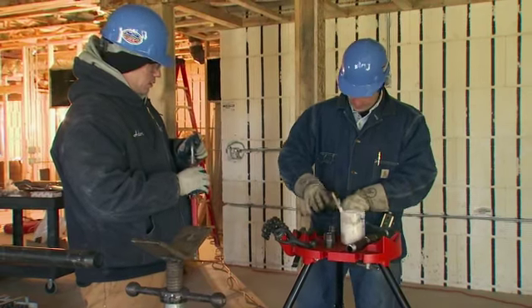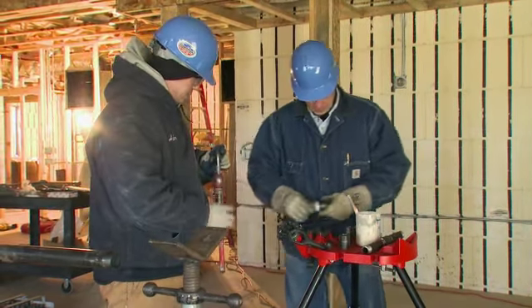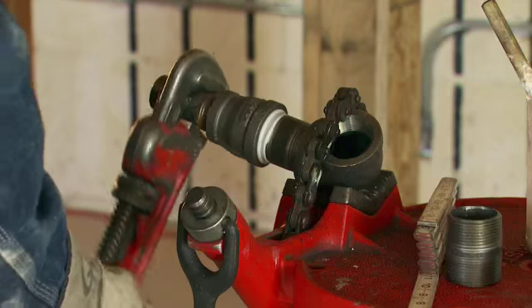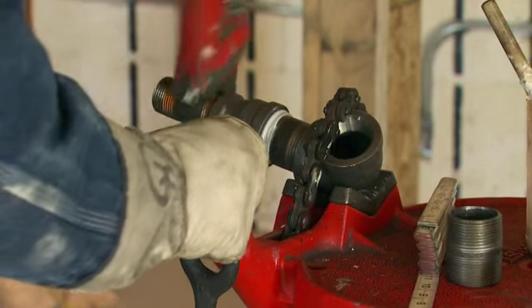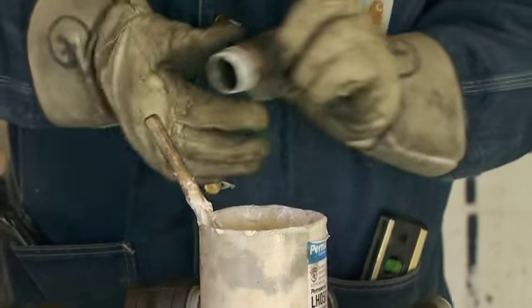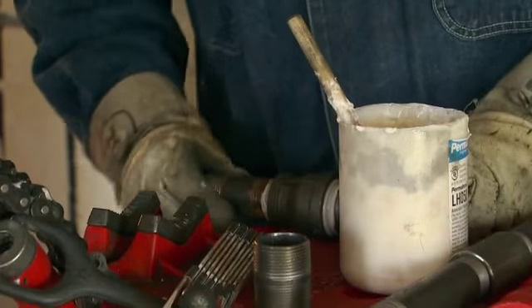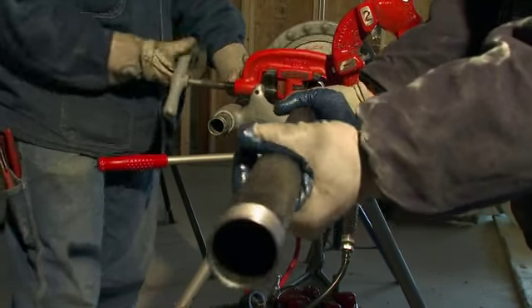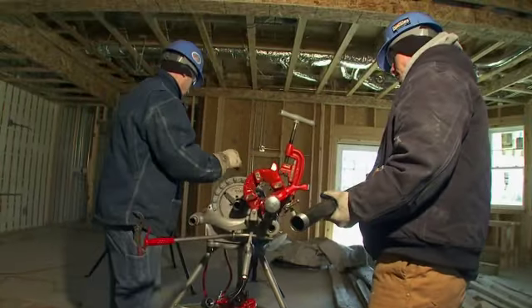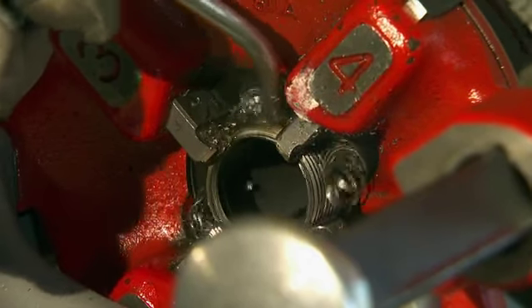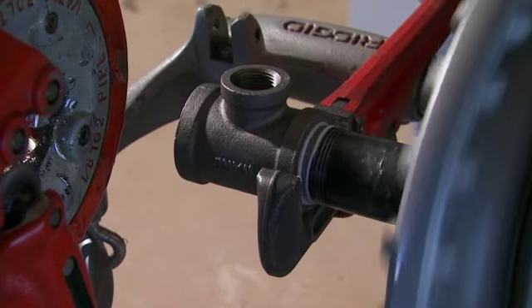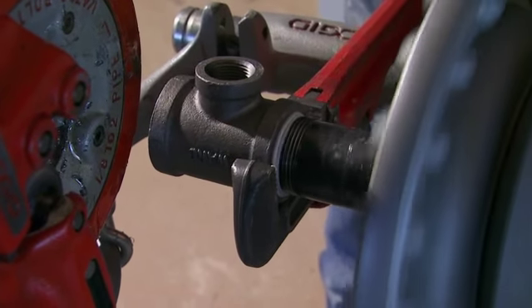We have different connection methods. On this project we're going to use two of them predominantly. One is threading, using screwed fittings, which is how we're putting in the gas system. That's a traditional means, so we have machinery on site that allows us to cut, thread, and assemble the screwed black pipe. We'll also use the latest method when we do the hydronic piping: a pro press or press fit type system where the copper tubing and fittings are joined, then crimped with a piece of machinery to provide a seal.